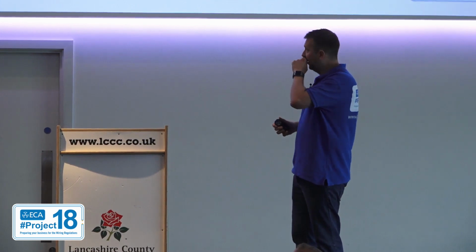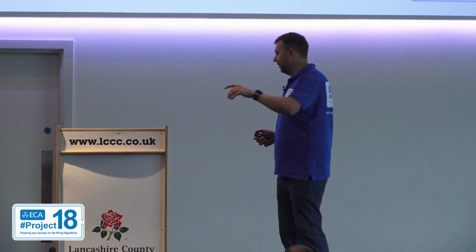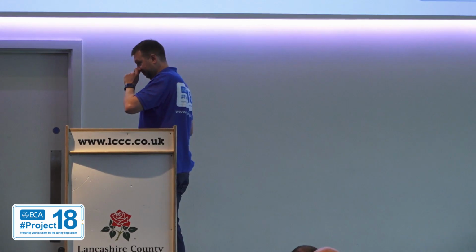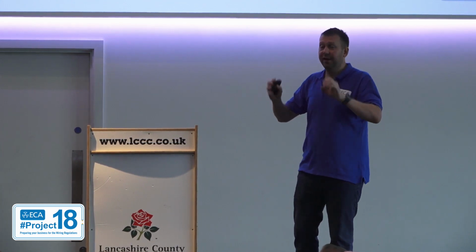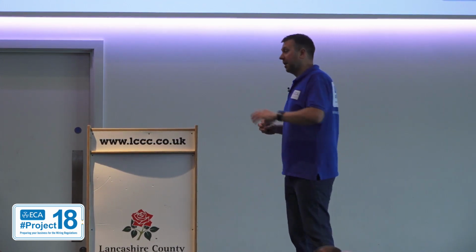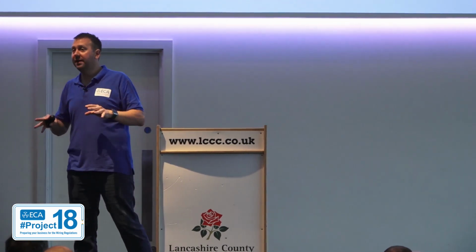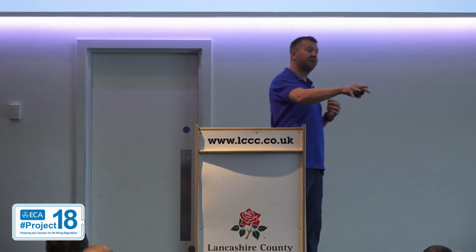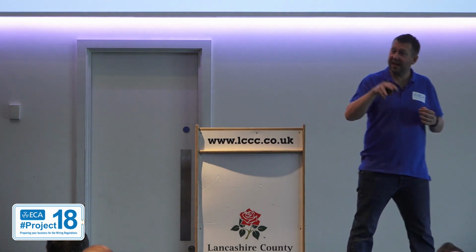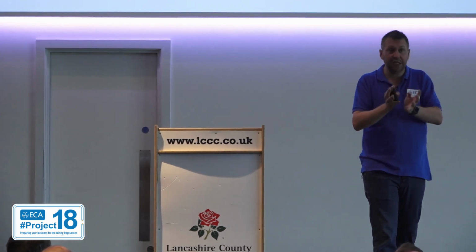The draft for public comment, when that was out, there was a proposal for all TN systems to have an additional earth electrode. Did you see that? It's not in. Didn't make it. There is information about TT systems and foundation earthing, but it's only for TT systems. The proposal to have an additional earth electrode on TN earthing systems has not made it. We don't have to do that. Do you know why? Partly because you guys voted against it. This is a second area where your thoughts and opinions genuinely made a difference.